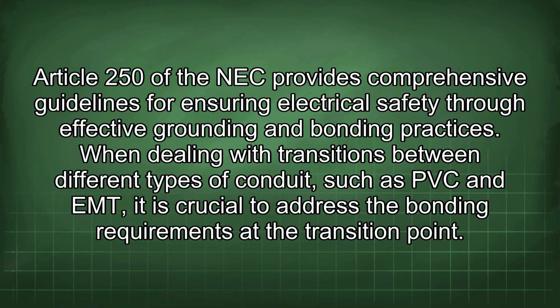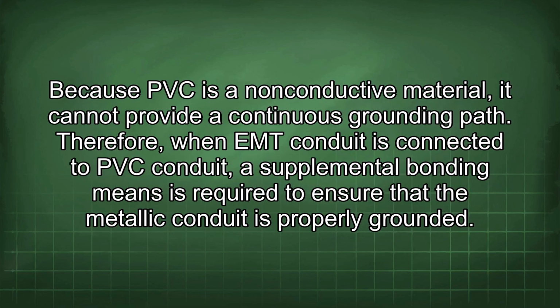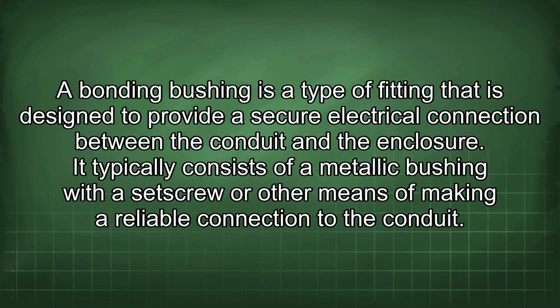When dealing with transitions between different types of conduit, such as PVC and EMT, it is crucial to address the bonding requirements at the transition point. Because PVC is a non-conductive material, it cannot provide a continuous grounding path. Therefore, when EMT conduit is connected to PVC conduit, a supplemental bonding means is required to ensure that the metallic conduit is properly grounded. A bonding bushing is a type of fitting that is designed to provide a secure electrical connection between the conduit and the enclosure.